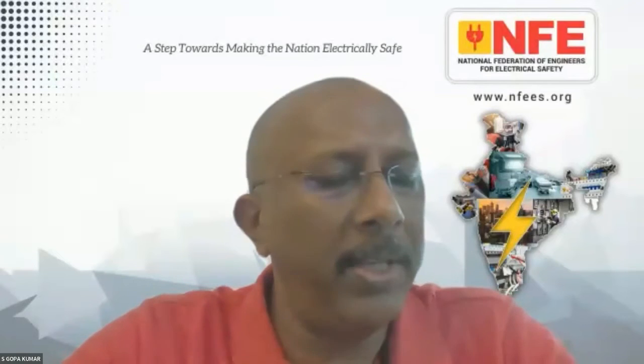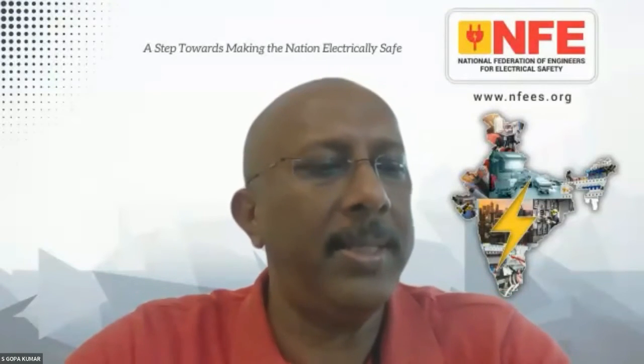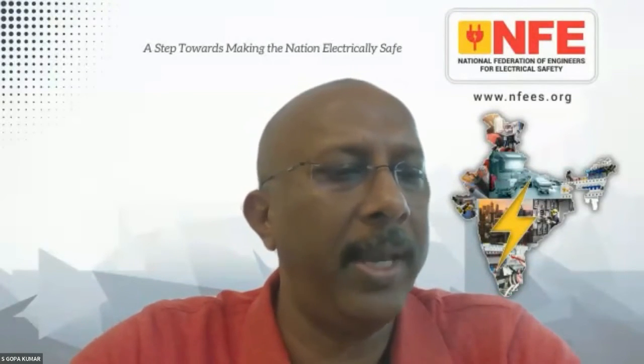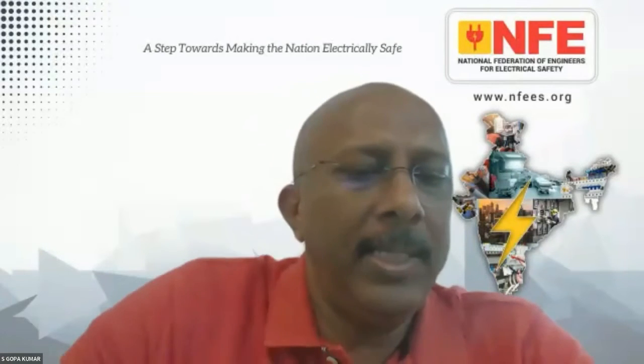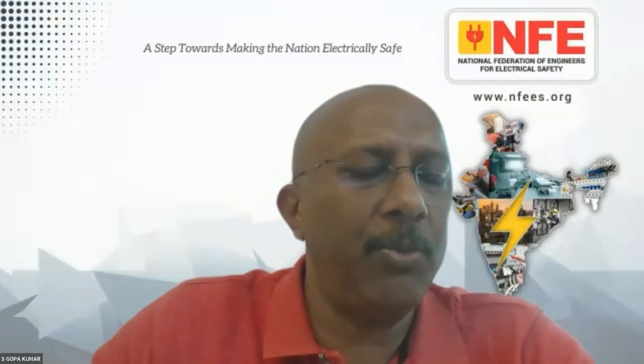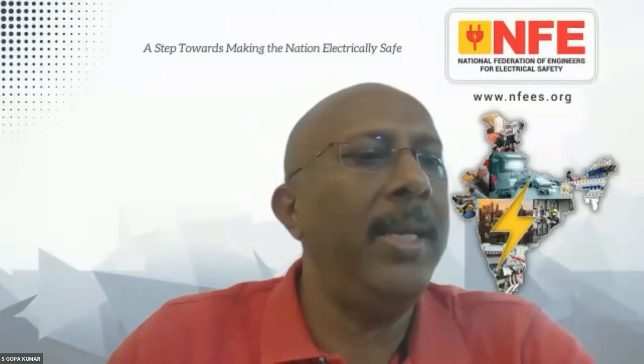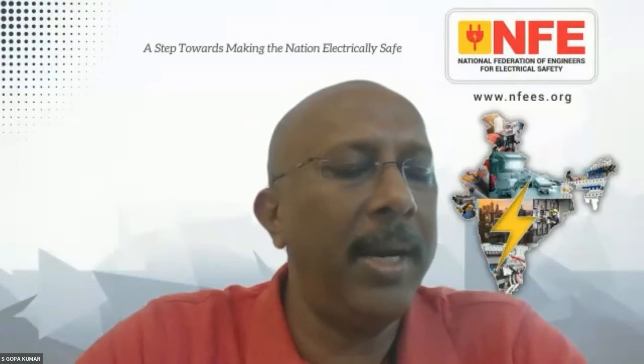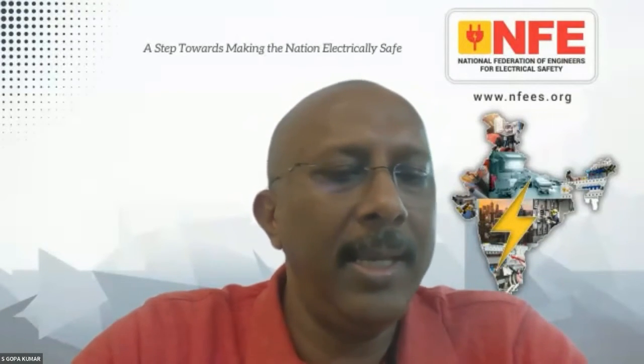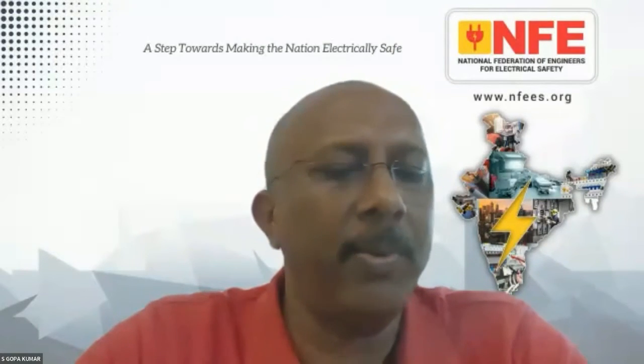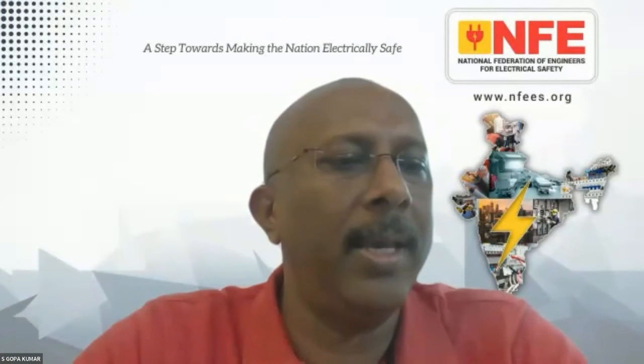The easy way is, please go to IS 15086 part 5. This is a standard which was made during 2020. It is from IEC 60099 part 5. This is talking about selection and application recommendations of surge arrestor, and the necessary protective measures for avoiding the tripping of the feeder are included there. Please refer to the standard. That is the easy way. Thank you. Yes, sir.